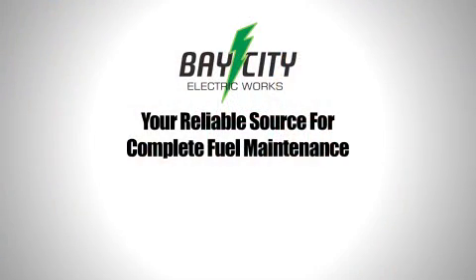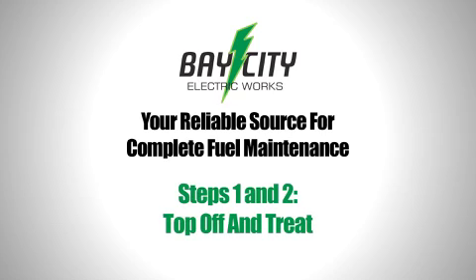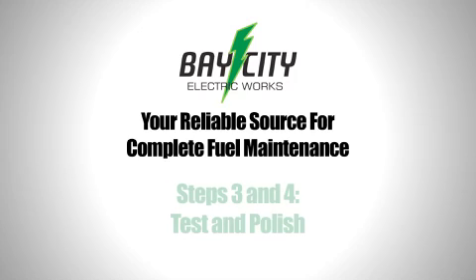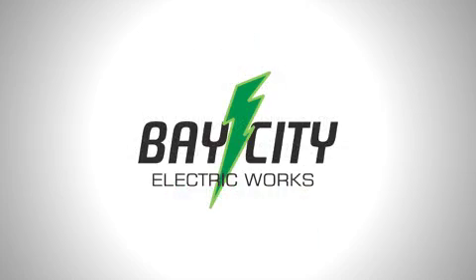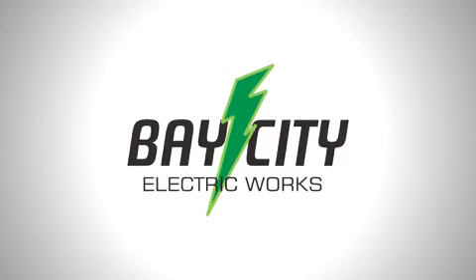Remember the Bay City Electric Fuel Maintenance Program — a full tank is best. Use steps one and two, top off and treatment, to prevent deterioration of your diesel and to maintain it in good condition. Use steps three and four to check for fuel deterioration and correction should it be required. A standby power system cannot do its job without good fuel maintenance.